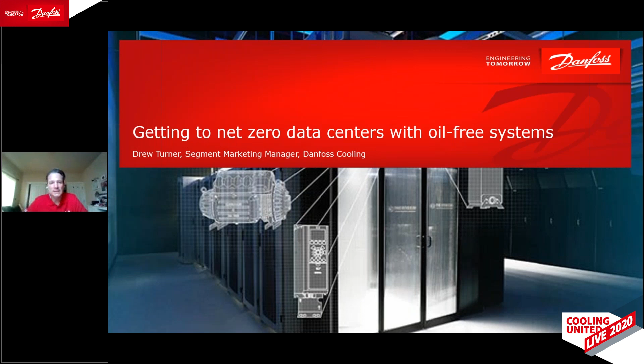What we see in terms of design trends for data centers is a combination of moving towards free cooling, increasing the cooling temperature, and reducing the heat rejection temperature, and also getting closer to the CPU. So it's a combination of related factors.